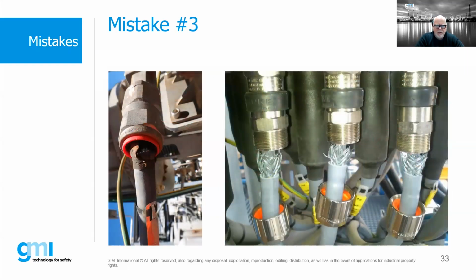Similar type situations, right? A question usually comes up on cable glands when we're doing inspections. We, as an inspector, there is, again, visual, close, and detailed inspections. One of the important things to note is that we never open up cable glands during visual or close inspections. We can touch them, we can look at them, but we don't open them up. We don't want to open up a cable gland unless the equipment has been de-energized, and in many cases we have a gas-free permit.